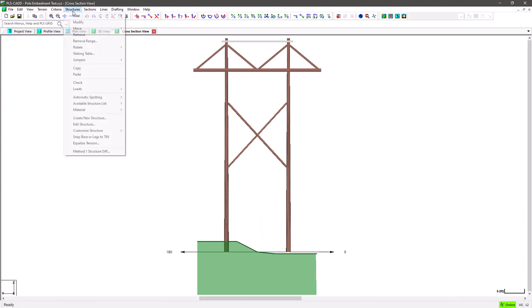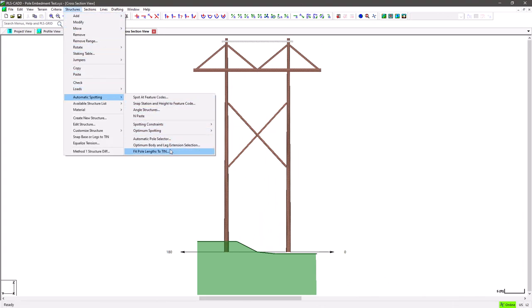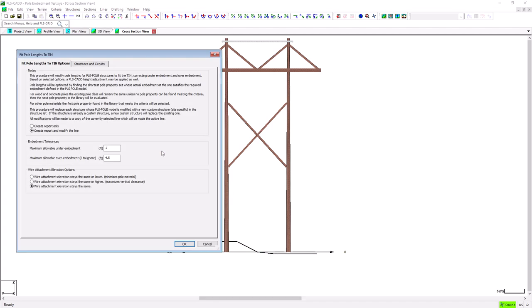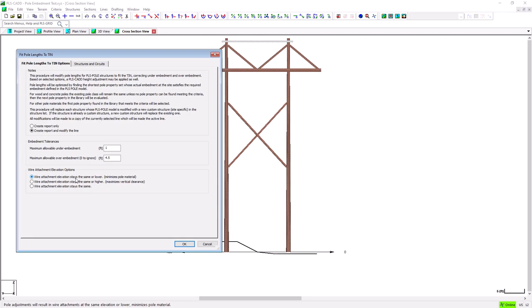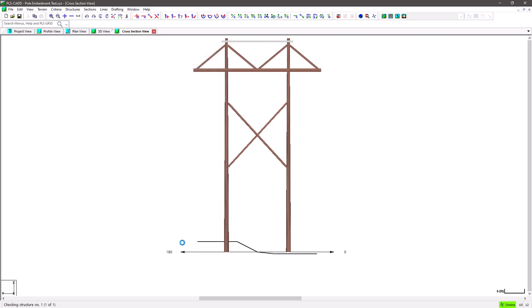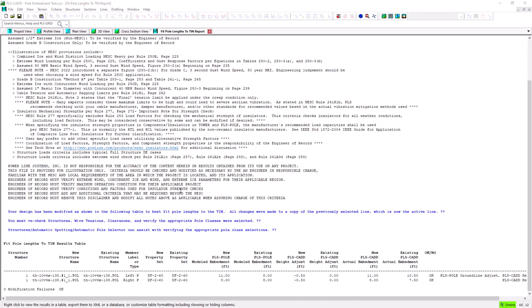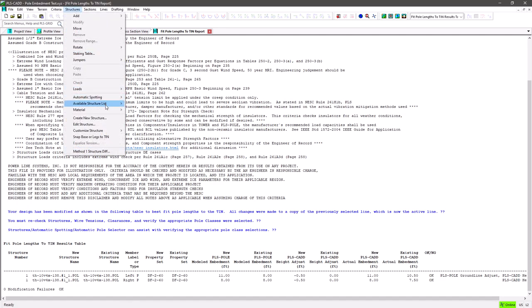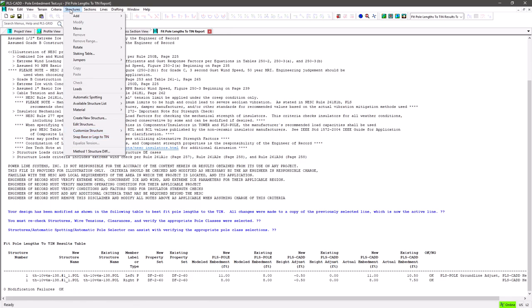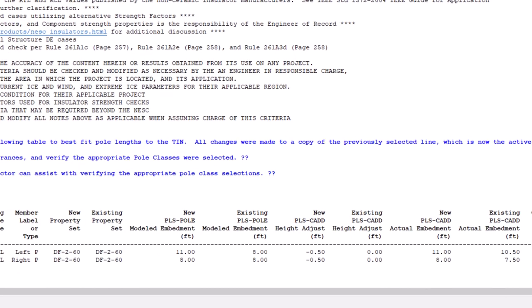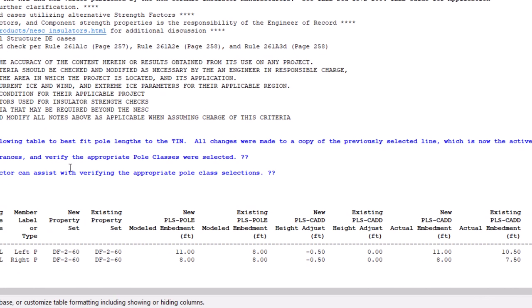Another way we can use this feature is to allow for structure height adjustments, which moves the entire structure up or down. Let's try this again with all the same settings, except let's check this option to lower the entire structure model. When we run the feature this time, the first thing the program does is it will lower the height adjustment such that all poles in the structure are either at or below the tin surface. This is analogous to running this structure's snap base or legs to tin command first, and will result in one of the poles having a typical standard embedment, i.e. 10% plus 2, and all other poles will need to be over embedded or shorter in pole length.